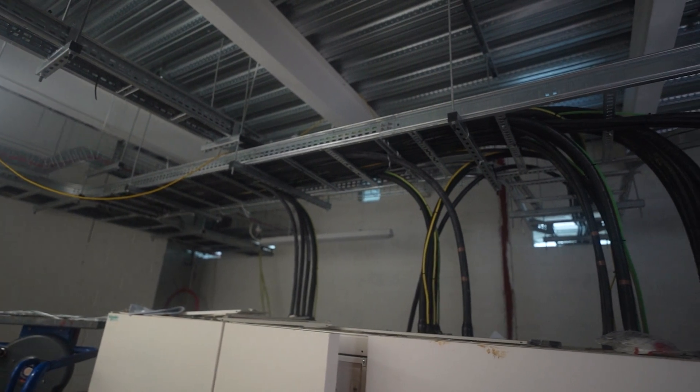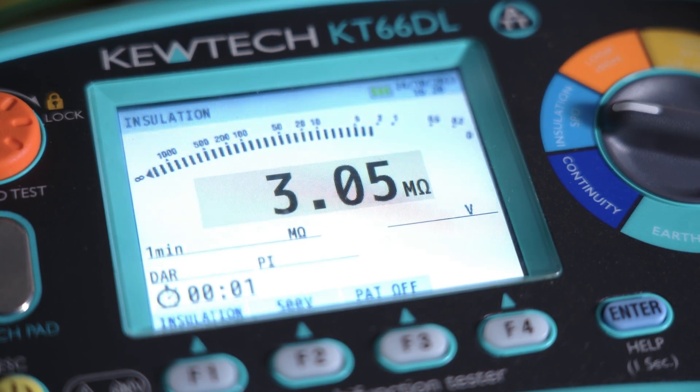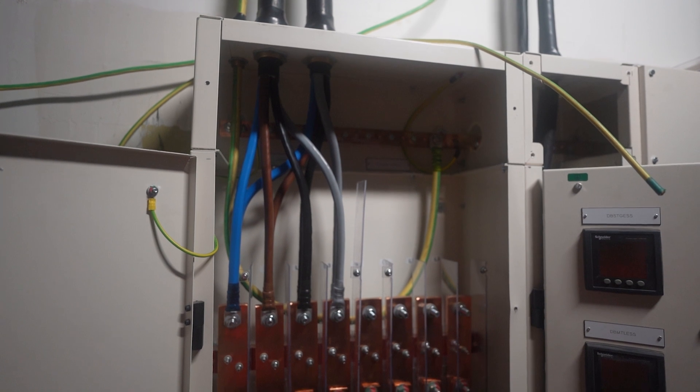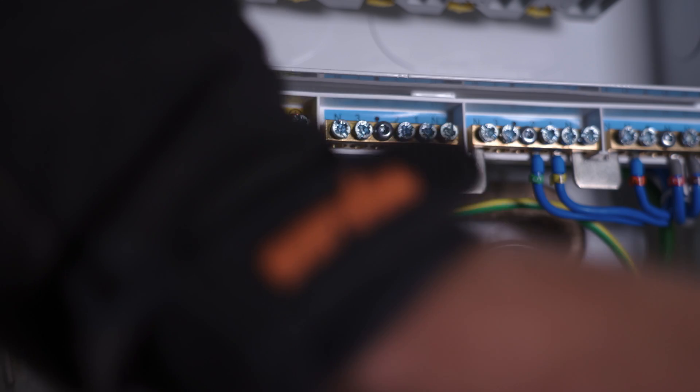When using the global IR test on complex installations you may get a low value, because more cable length creates a lower overall insulation resistance. In this case, subdivide the installation into its component parts to carry out the test reliably. With both test methods it's important that two-way switching is operated and tested in all combinations to verify the full extent of the wiring — making sure the test voltage is applied to every strapper and every bit of the circuit.